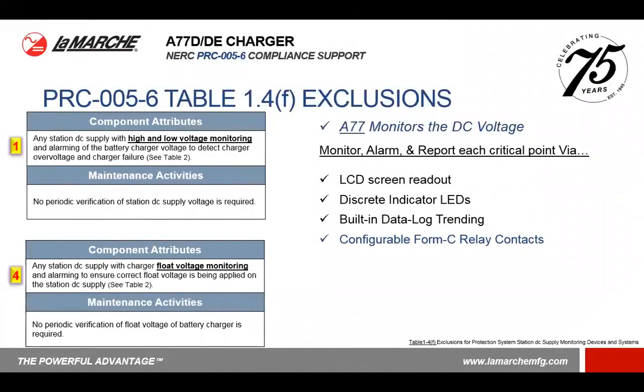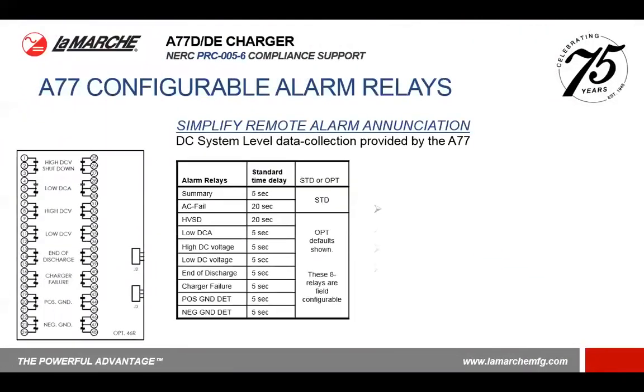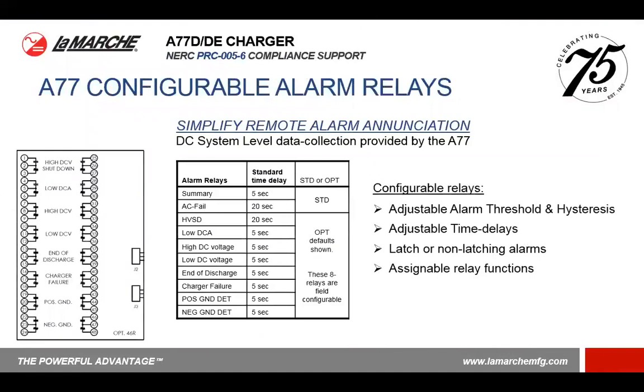For immediate annunciation that the voltage is out of spec, we have configurable Form C relay contacts. The Form C relay contacts on the A77 are fully programmable. The standard configuration that ships out of the building includes these alarms. Our time delays are programmable, but we can also program them to be latching or non-latching alarms. We can assign the relay functions and have different unique functions with them.